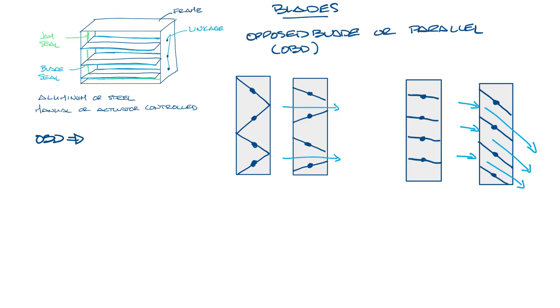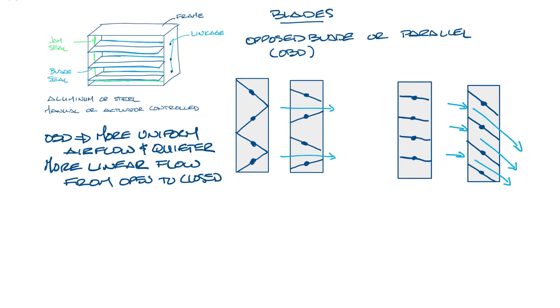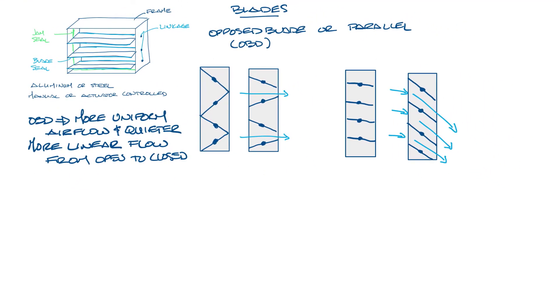OBDs not only have more uniform airflow and a little quieter, they also have more linear characteristics from the open to closed position. So they're good through a broader operating range. Parallel blade dampers have a steeper relationship so the more they open, the flow increases more rapidly. That said, most controllers and sensors are measuring and controlling the airflow, not damper position, so they can compensate for that.